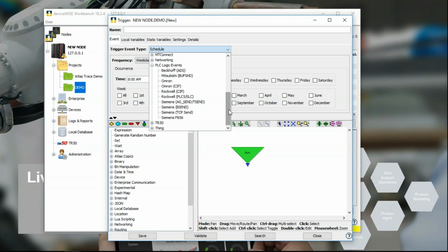For example, test results. You're doing a batch, and there's about 20-40 analog values that have to be sent. When the batch is complete, you put them in a contiguous data block, maybe like a UDT in Rockwell, and then send it as a network instruction.